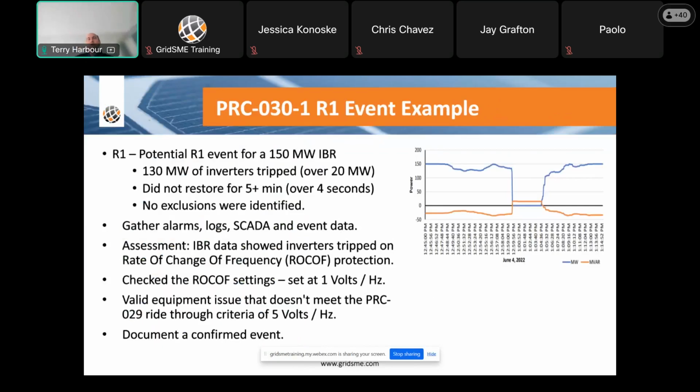That is a great question, Jay. I think I may have used an example and referenced PRC-29, but I think these are standalone. PRC-30 is a learning requirement. So if you have these megawatt trips or inverter trips for events on the system like they had in the Odessa events, NERC wants you to start investigating.